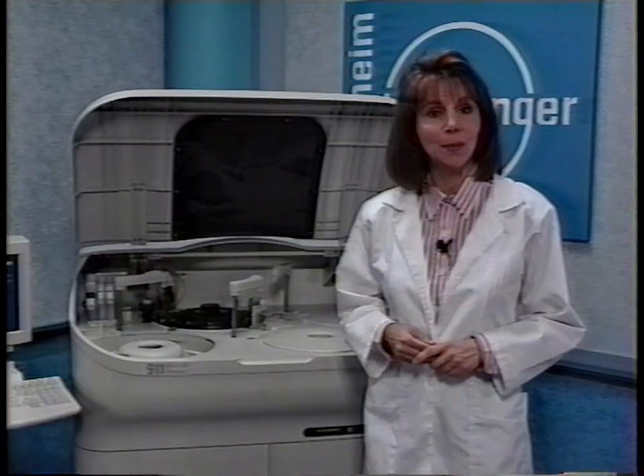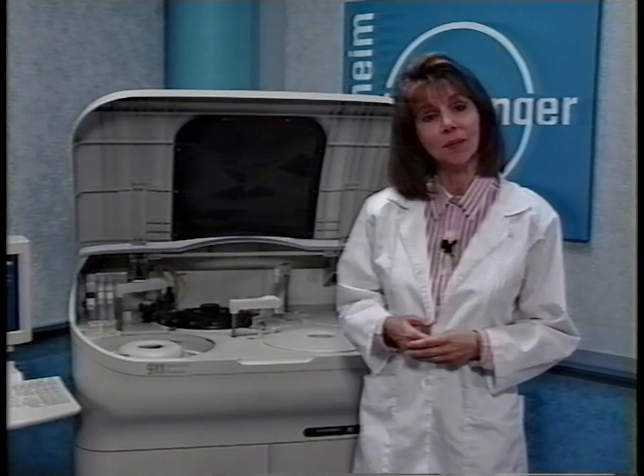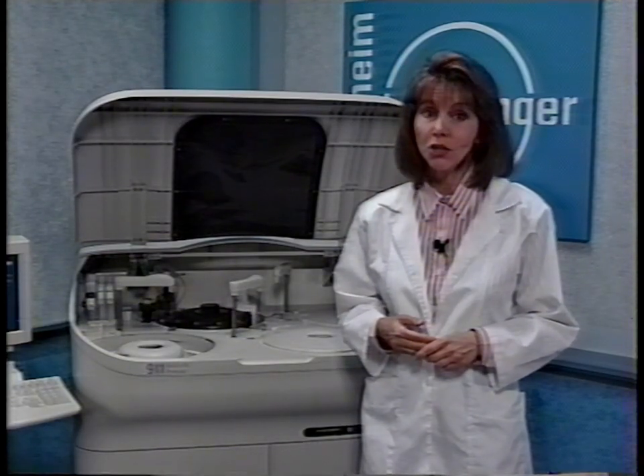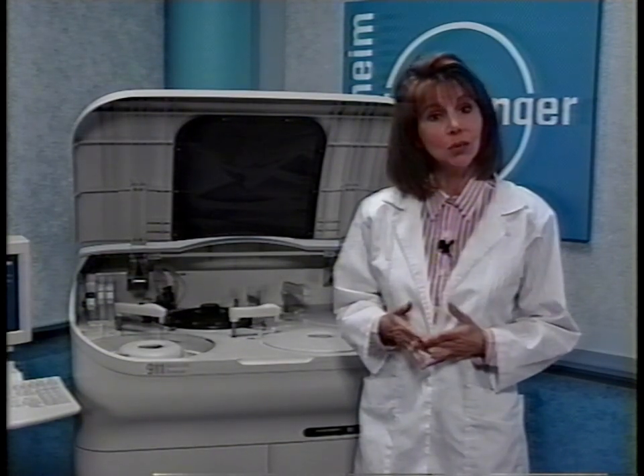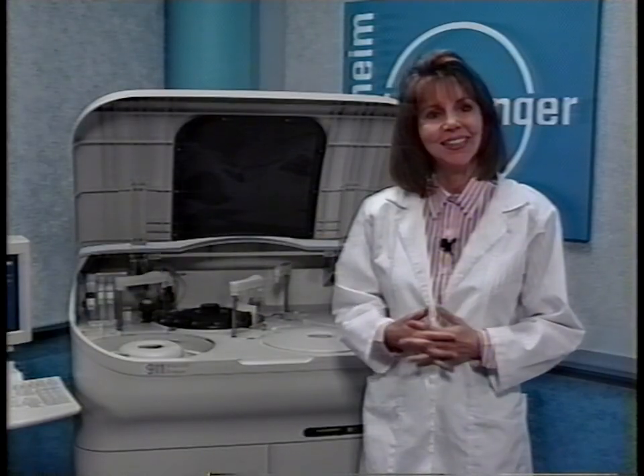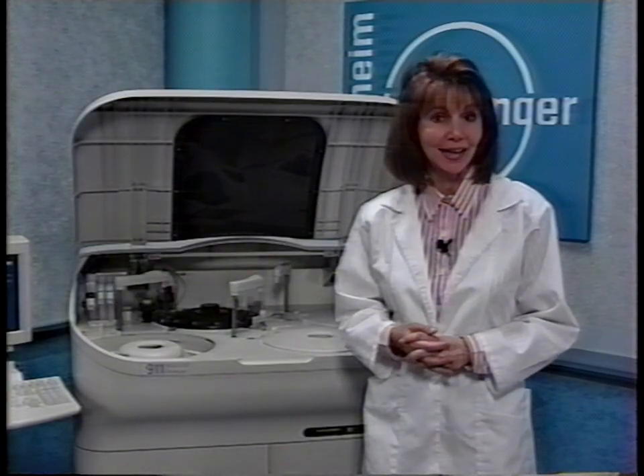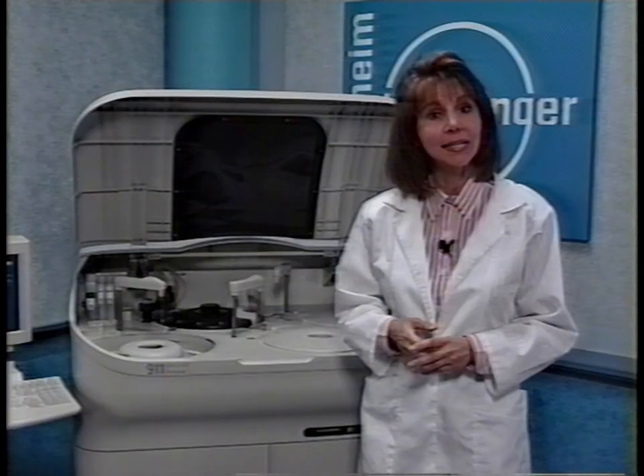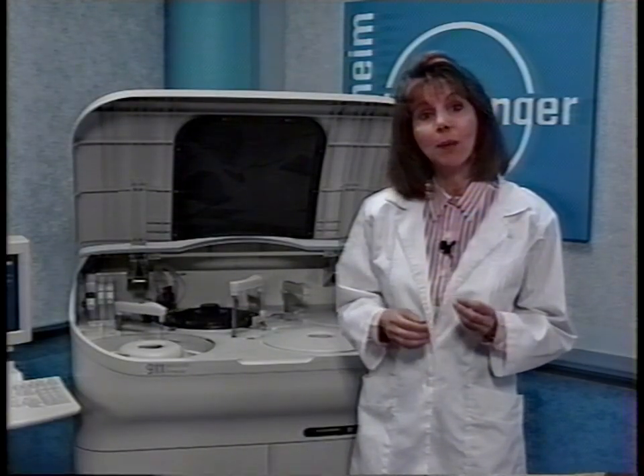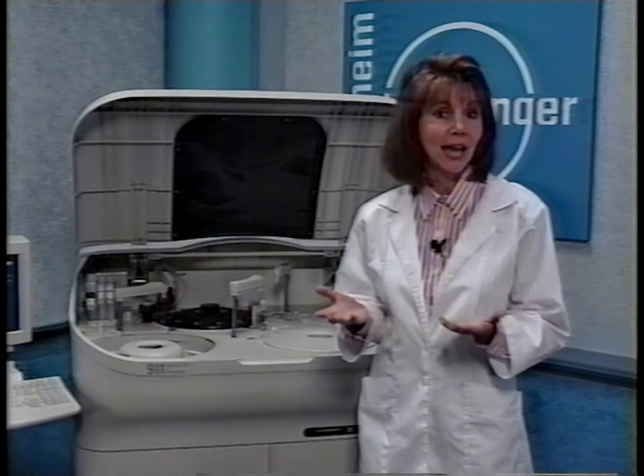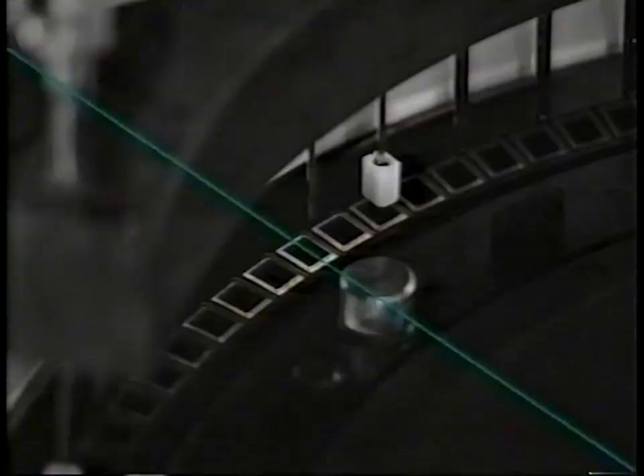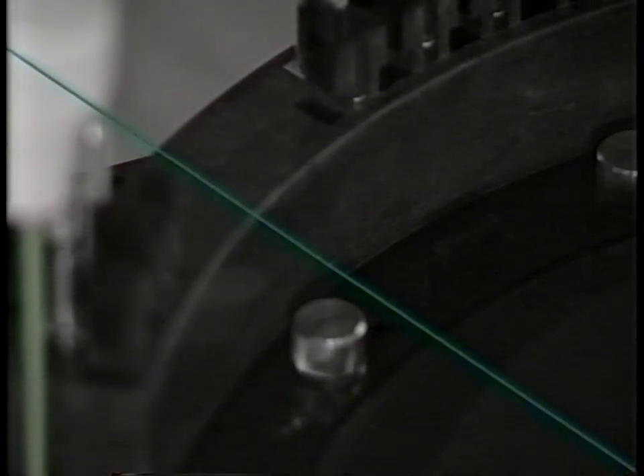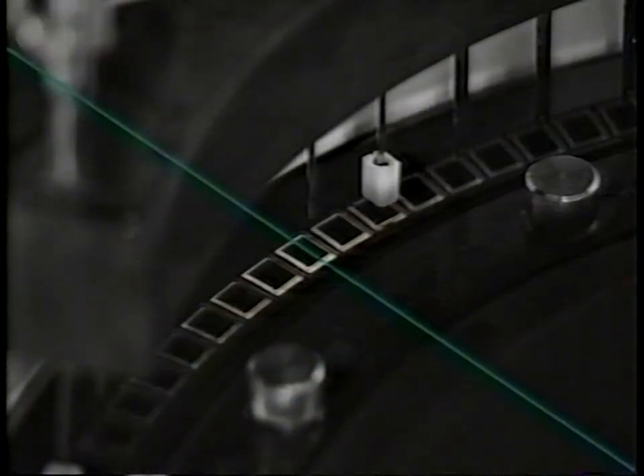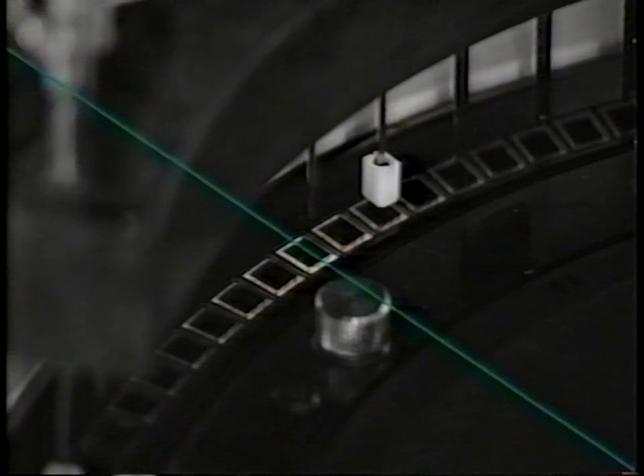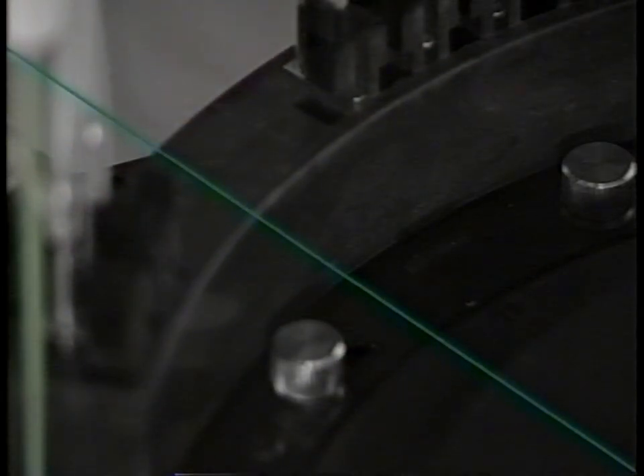An automatic sample dilution can be programmed into the system. The R1 reagent probe can also add, instead of a reagent, a diluent such as saline or water. The diluted sample is stirred by the stirring paddles. The sample probe then aspirates an aliquot of the diluted sample and places it into a new cell, where the actual reaction will occur. The reaction disc rotates the cells through the light path of the photometric measuring system. The absorbance of each cell's reaction mixture is measured by the photometer as the reaction disc is turning.